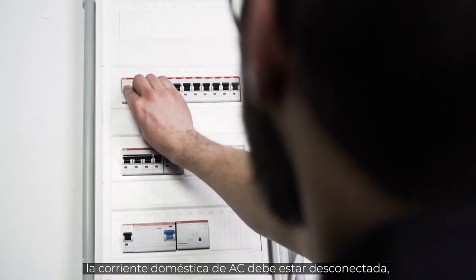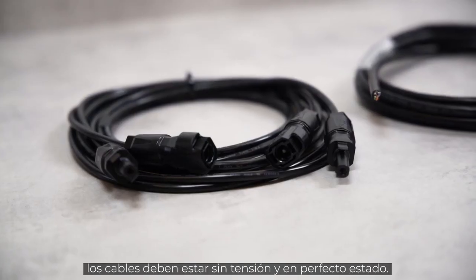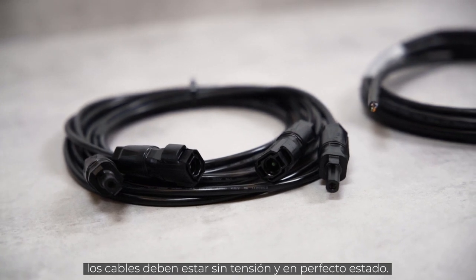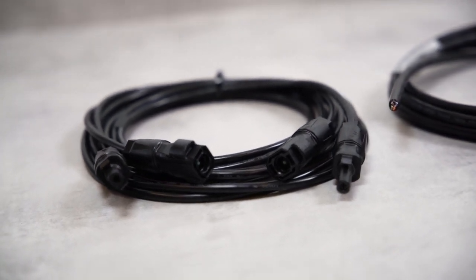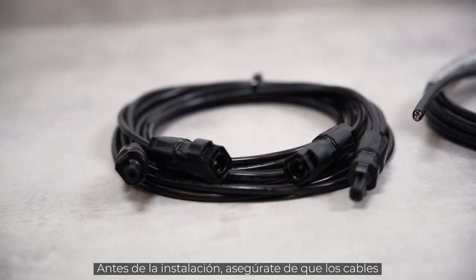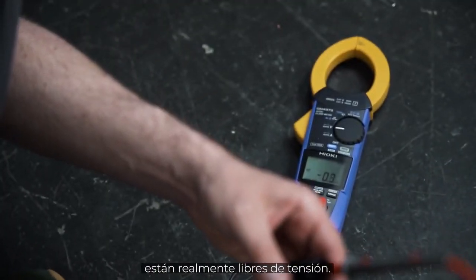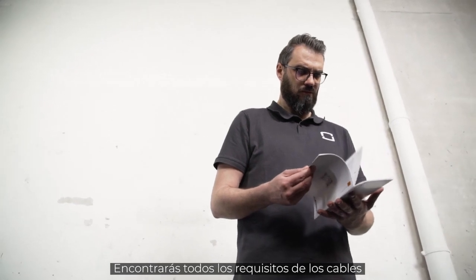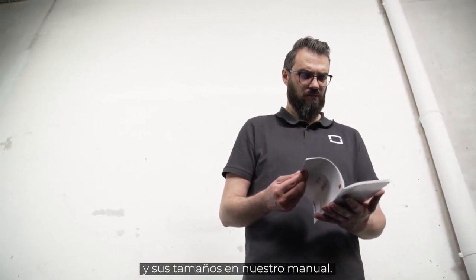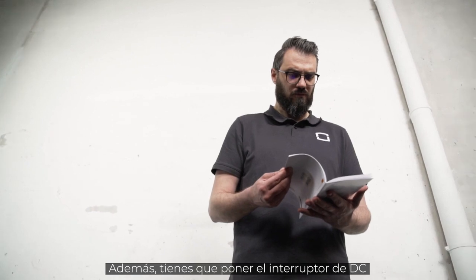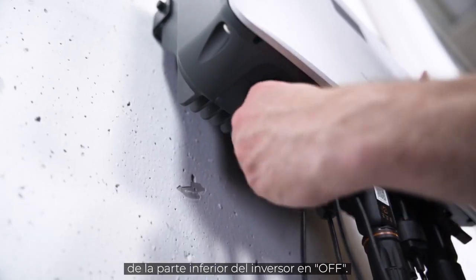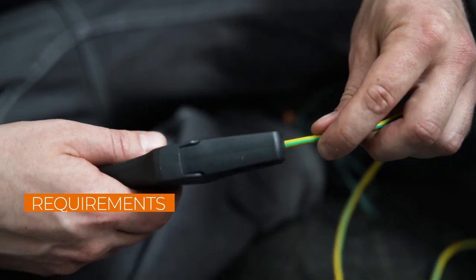Before the inverter can be connected, the AC home circuit breaker must be disconnected, the cables must be de-energized and in perfect condition. Before installation, make sure by measuring that the cables are really voltage-free. You will find all cable requirements and wire sizes in our manual. Furthermore, you have to set the DC switch at the bottom of the inverter to off.